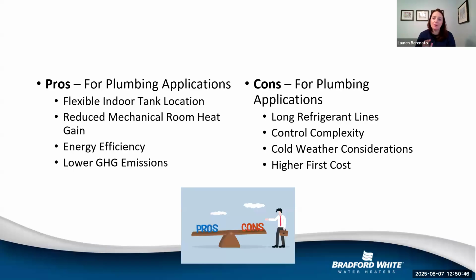Now, just talking about some of the pros for plumbing applications and some of the cons that might be. For pros, reduced mechanical room heat gain. Since the compressor's outside, it won't reject the heat indoors, so helpful for maintaining climate control. For cons, control complexity, for example, staging and controls are more complex than conventional water heaters, especially when balancing with mixing valves or backup heaters.